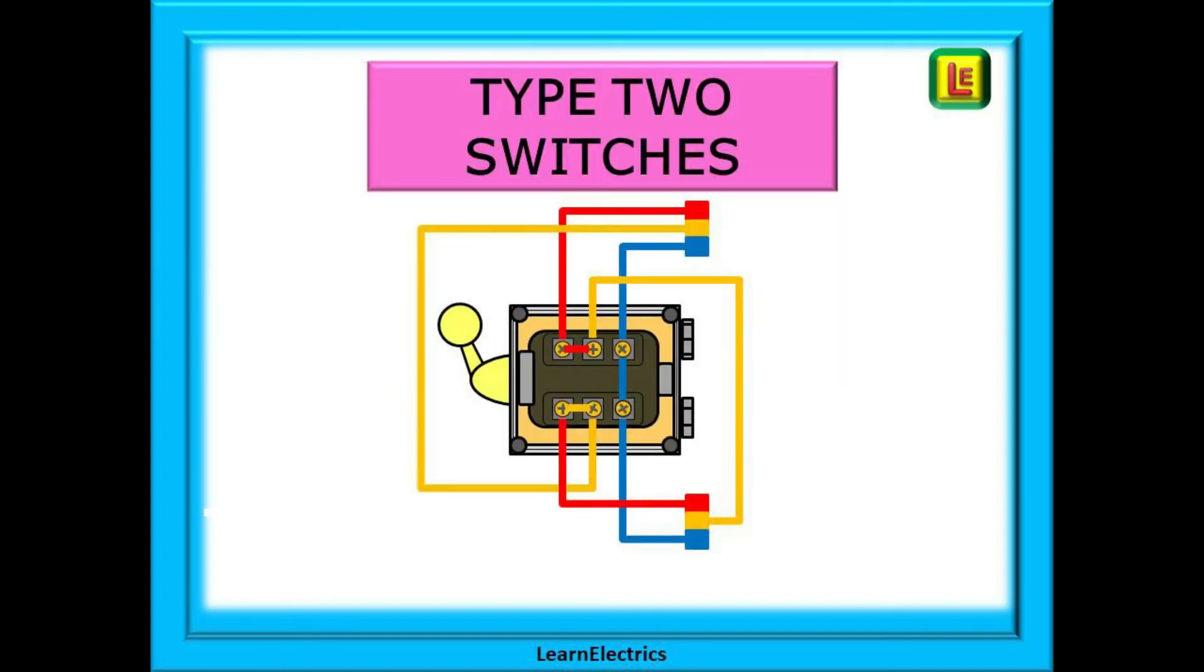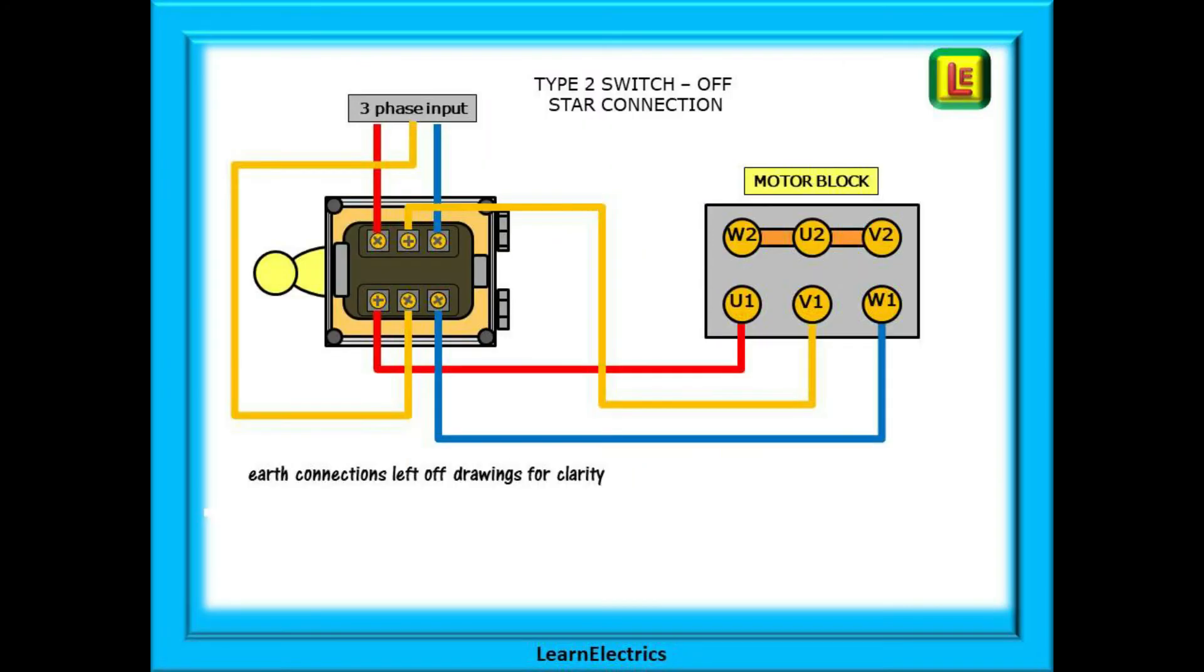Take a look at the type 2 switches now. Remember that the L2 input must be positioned on the opposite side of the switch to the L1 and L3 connections. In the off position look carefully at the positioning of the input cables. L2 input is on the opposite side to L1 and L3.